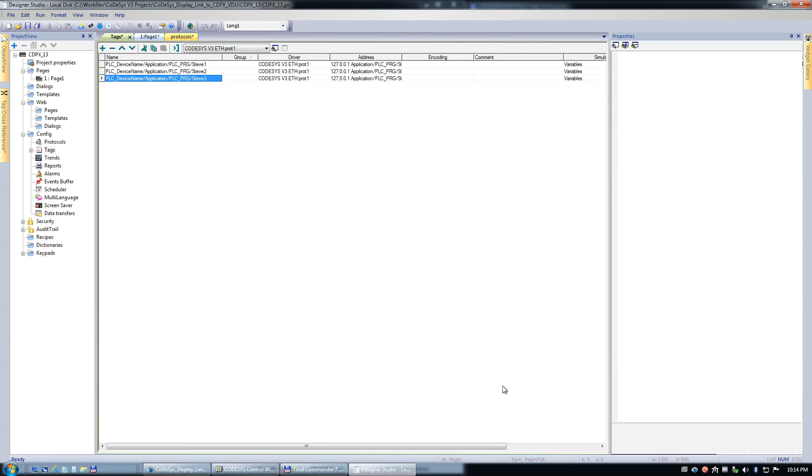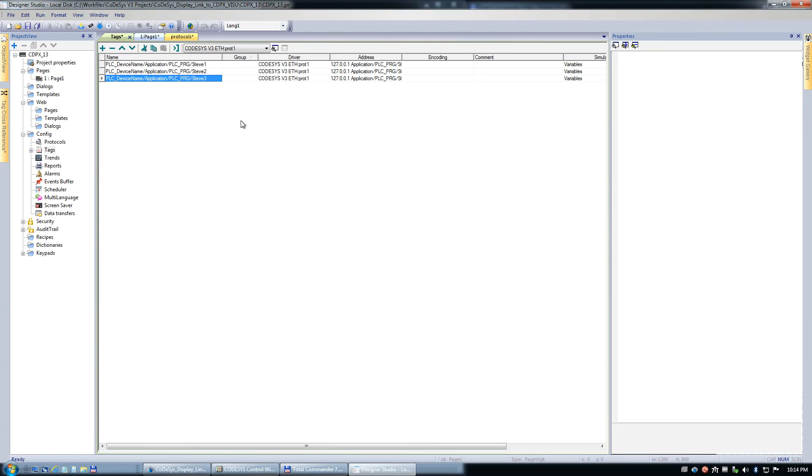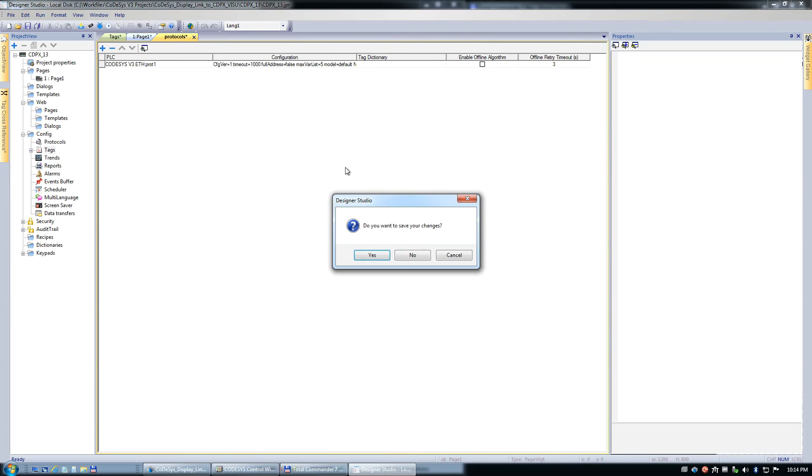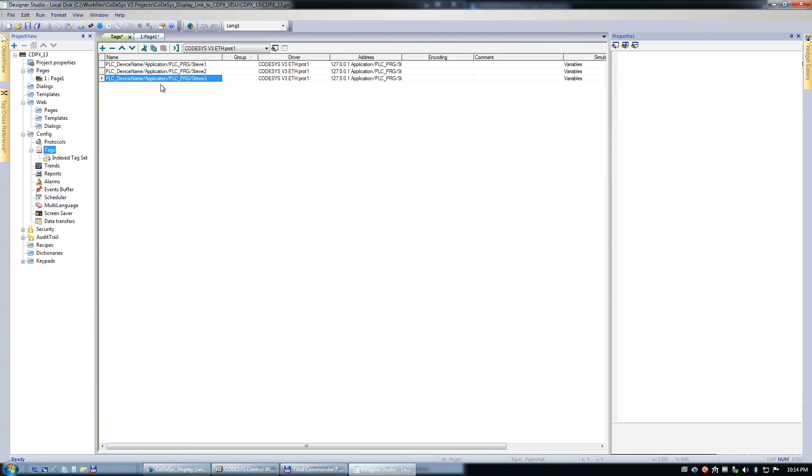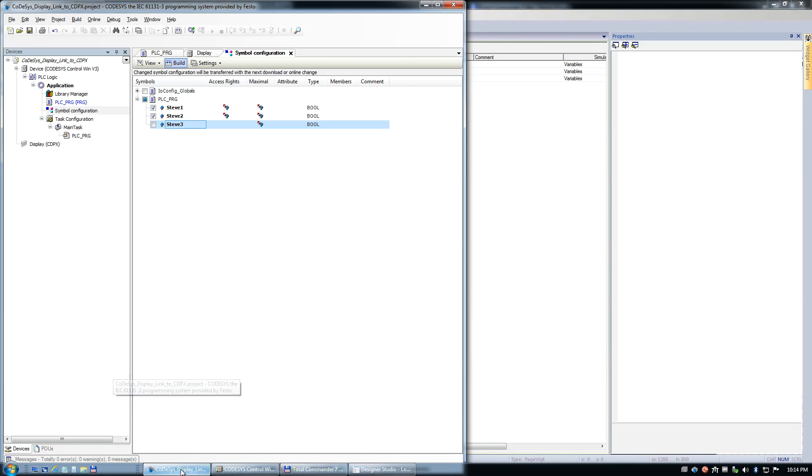So that's a lot better, don't you think? I mean, it's taking us the same amount of time. But now, every single time you make a change to the PLC and add a tag, or you want to add something or remove something, it'll update. Now, if you want to delete the tags and you do that in the PLC, I don't believe it deletes them. You have to kind of do that manually. I'm going to hit save, come down here. You have to basically delete the tags. So it brings them in for you, but you have to delete them manually. You could have some remnants of code laying around if you don't deal with things properly.